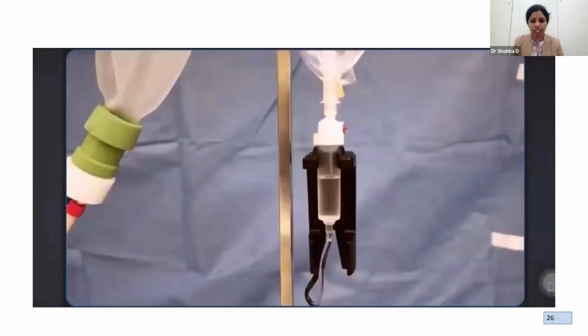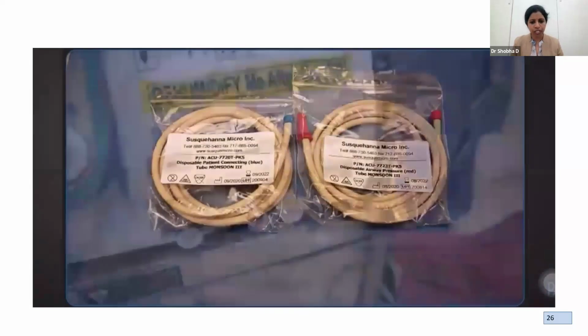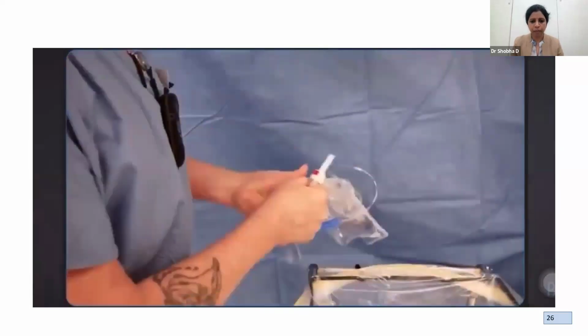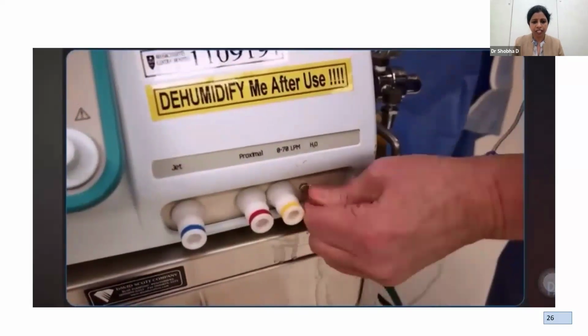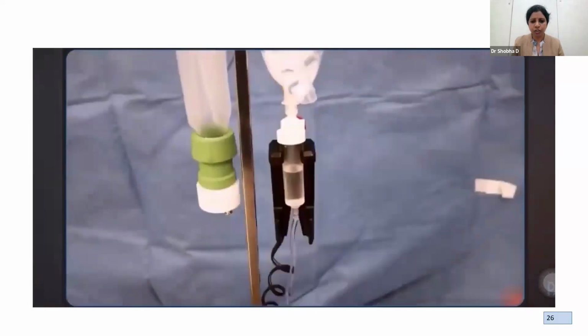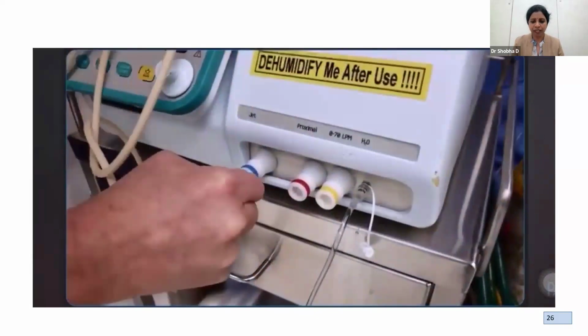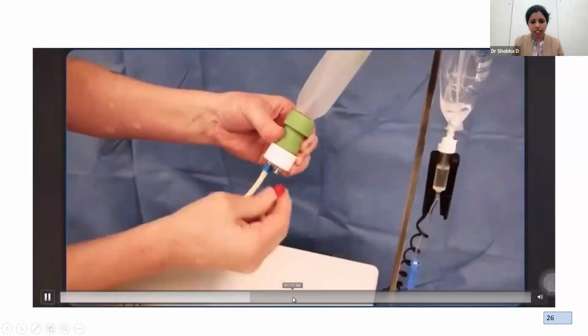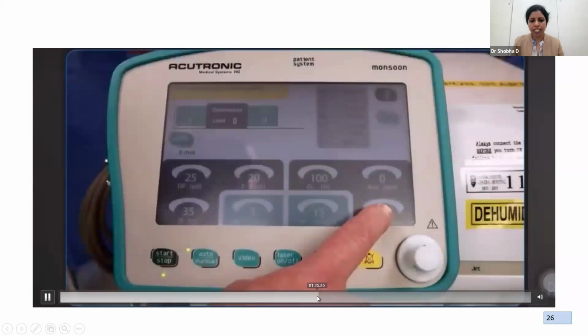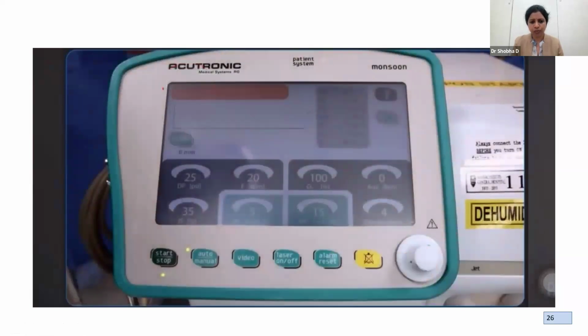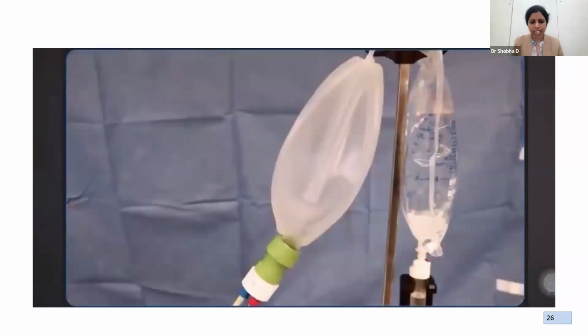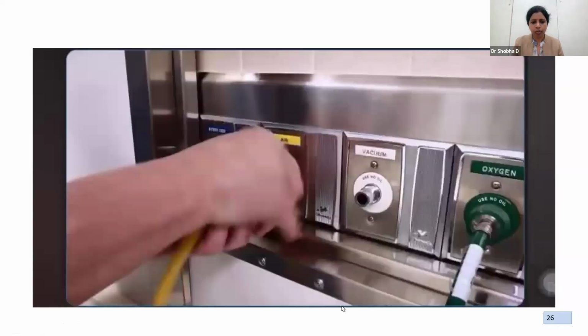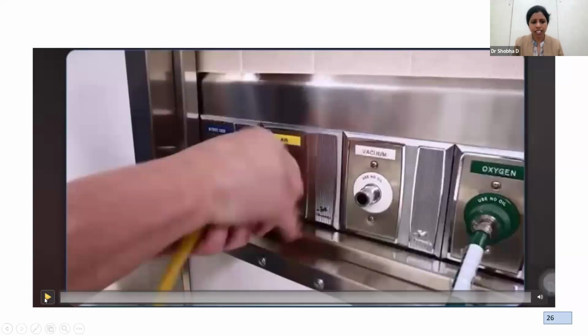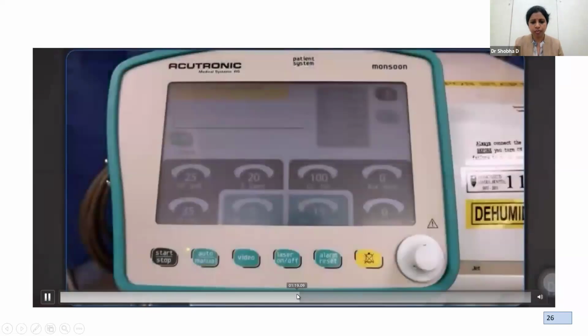So make sure that when we connect, the air is completely purged out of the tubings. So how do we set this up? Once it is connected, this is the drop sensor. When there is no drop falling into it, again it will give an alarm. So make sure these tubings are connected before the ventilator is put on. Priming of the ventilator is done by setting the humidification, usually at the level of 4. There is an opening present on the connector of the test lung.